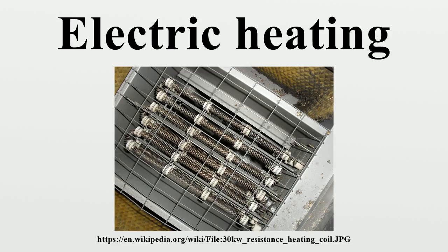Domestic immersion heaters. Domestic immersion heaters, usually rated at 3 kilowatts and on a 1.5 British standard pipe screw plug in the UK, run on the normal domestic electricity supply, but consumers may also take advantage of a cheaper, off-peak electricity tariff such as Economy 7. In a typical off-peak installation, a lower immersion heater is connected to the separately switched off-peak heating circuit, and an upper heater is connected to the normal circuit via its own switch. The consumer then has the option to top up the available hot water supply at any time, rather than waiting for the cheaper supply to turn on.